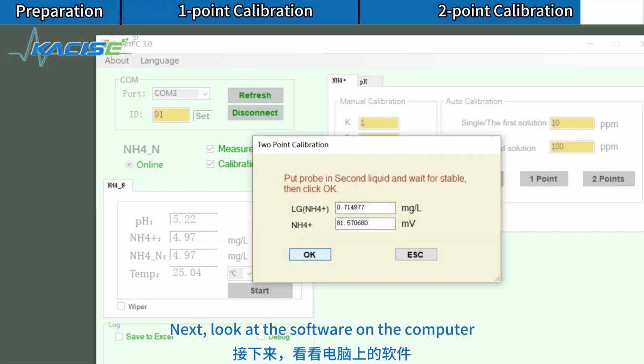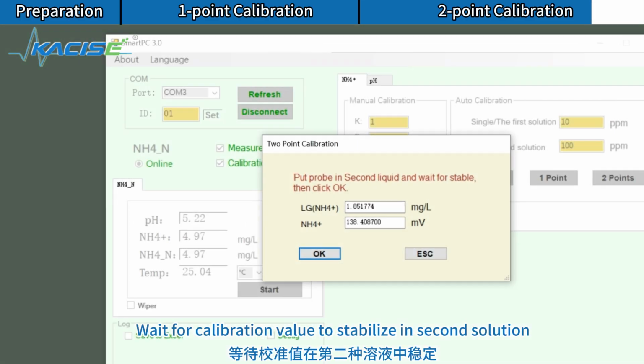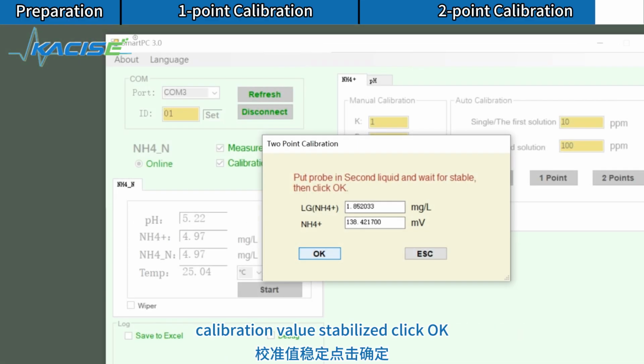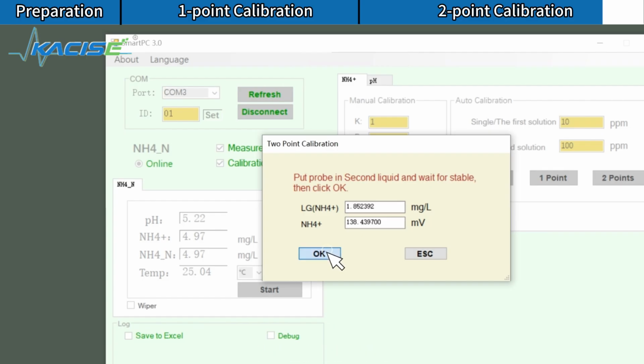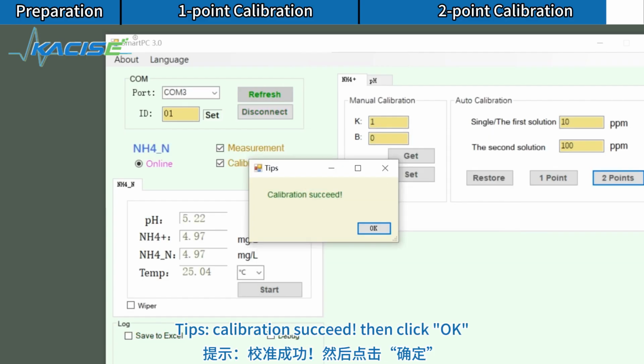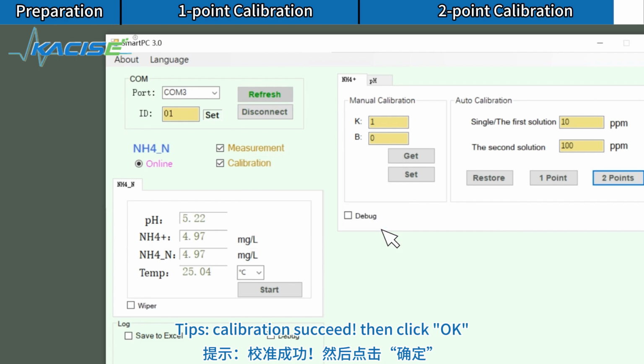Next, look at the software on the computer. Wait for the calibration value to stabilize in the second solution. Calibration value stabilized. Click OK. Tips: calibration succeeded. Then click OK.